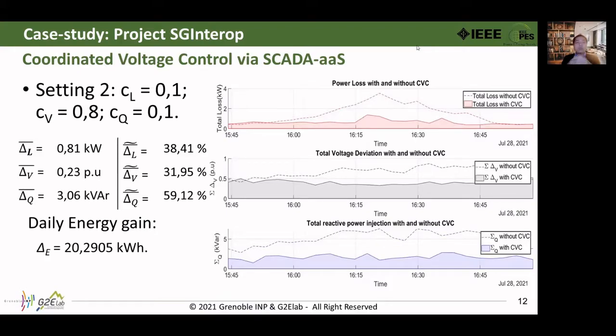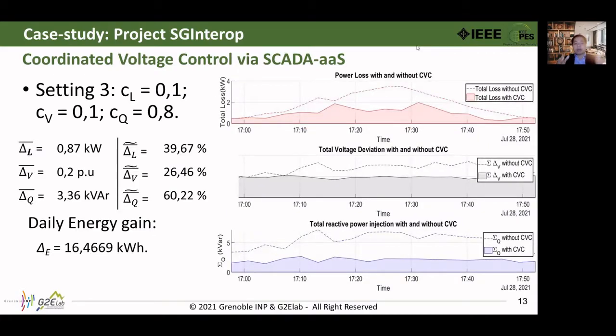In setting 2, we put a lot of weight on the voltage deviation criterion, and as you can see, the delta V has been increased up to 32%. However, it comes with a compromise of the delta L and delta E. In setting 3, we consider a lot of weight on delta Q, on the reactive power injection, and less weight on delta V and delta L. So in this case, despite the fact that we increase a little bit of delta Q, we can see a reduction in terms of delta L and delta V, and the daily energy gain is the lowest of the 3 settings.